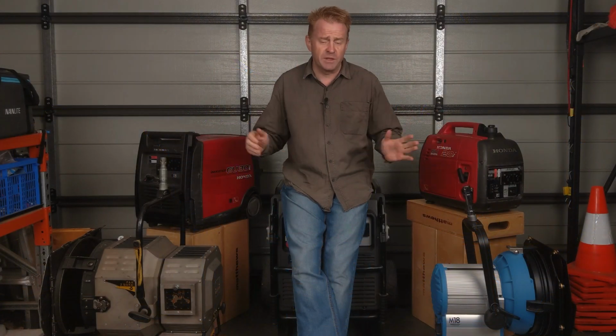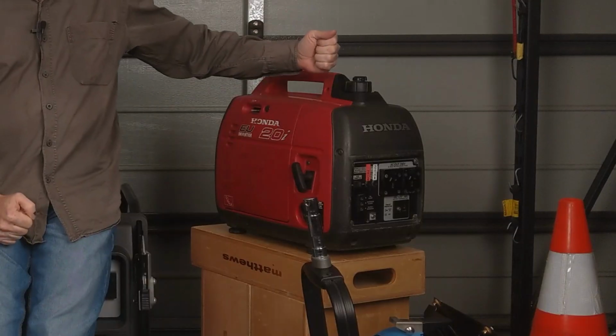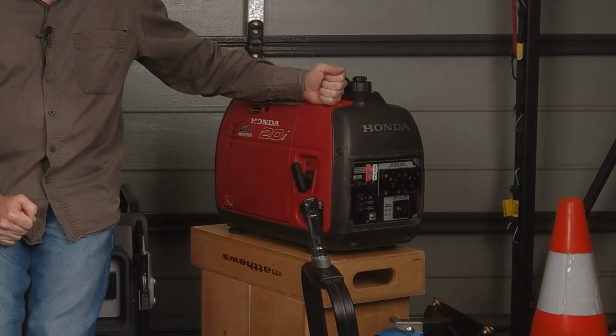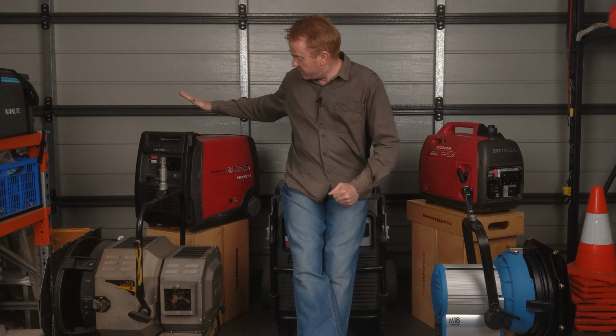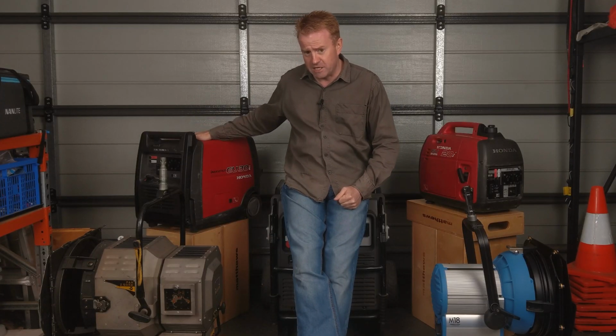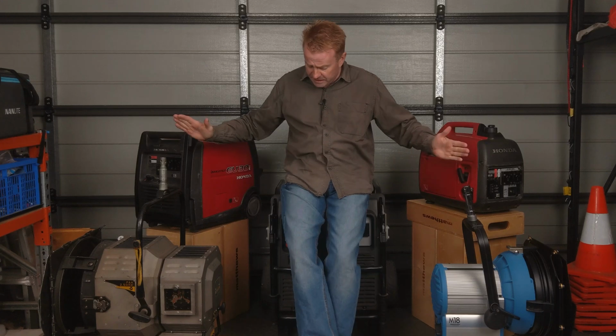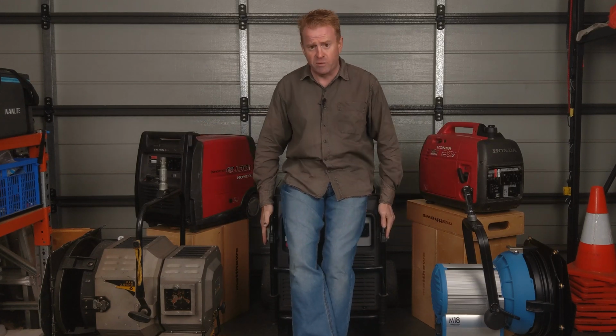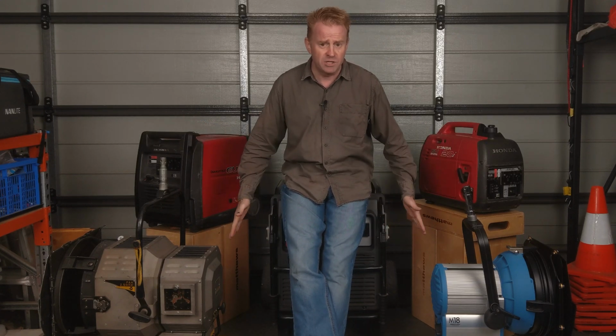Alright, so let's talk about the generators first, because that's where the most misperception is. A lot of people have a misperception of how much power comes out of the generator and for how long. So they're the two things we need to discuss. Okay, so basically I'll get into the maximum ratings of the generators first. So this is a 2 kVA generator, so that's a maximum that it's rated at. This is a 3 kVA generator, that's the maximum it is rated at, and I'm sitting on a 7 kVA generator, which is the maximum it is rated at.